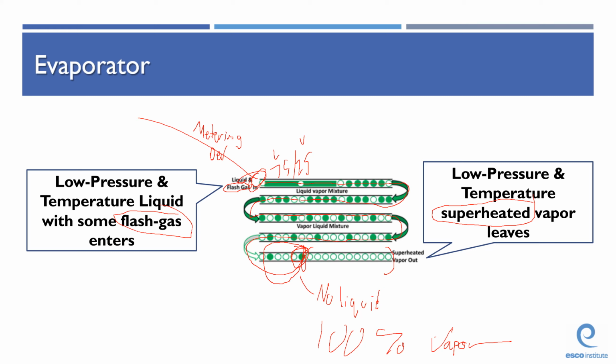Another symptom, if we get enough liquid back to our compressor, is that liquid gets into the compression mechanism. The compression mechanism can't compress that liquid. So it's either going to A, tolerate it, or B, destroy itself. So you never know. It's just cheap insurance to always have a vapor going back to your compressor. And that's one of the main things these systems are designed around.